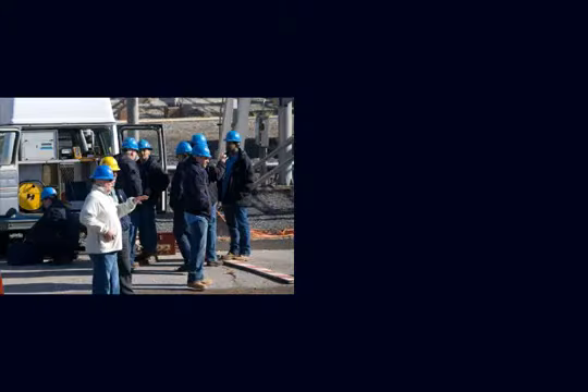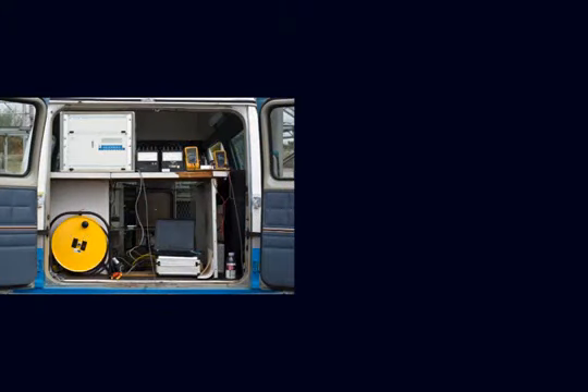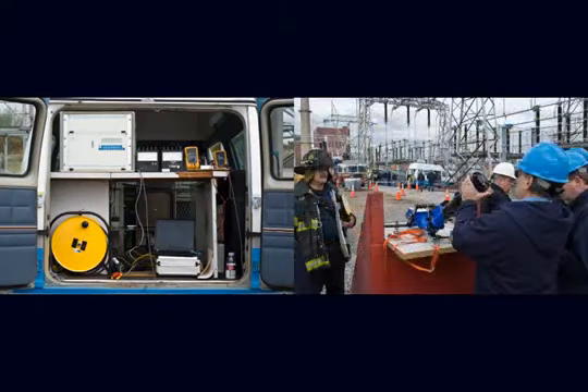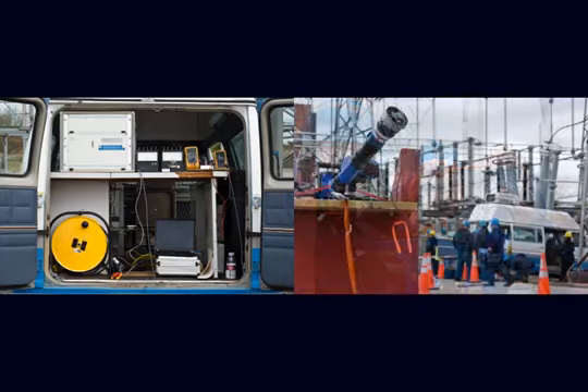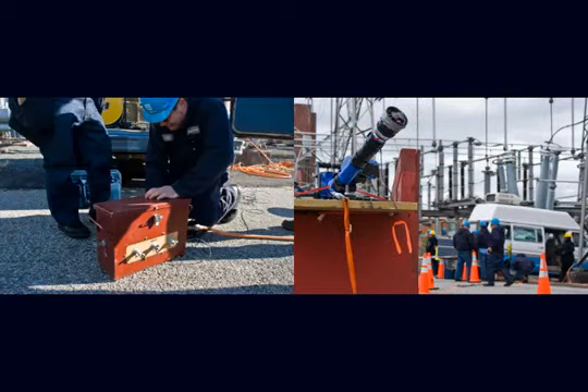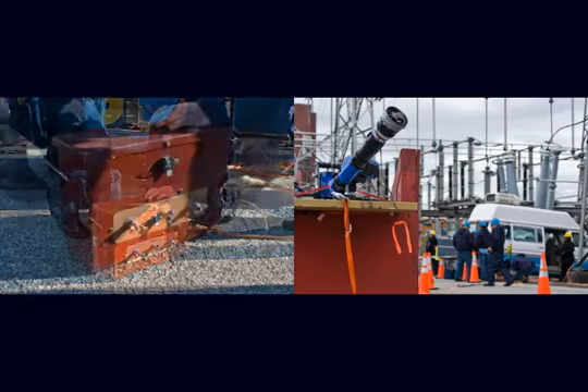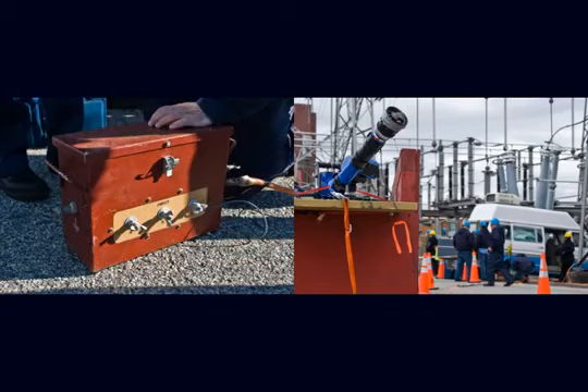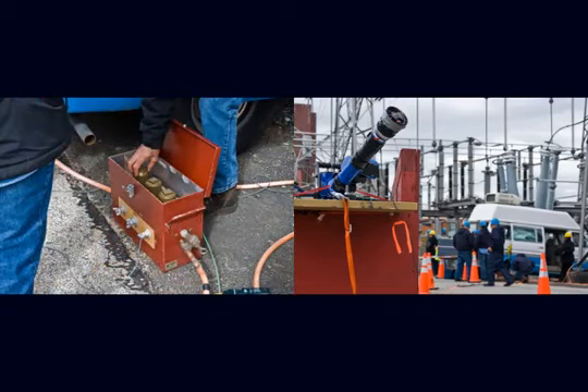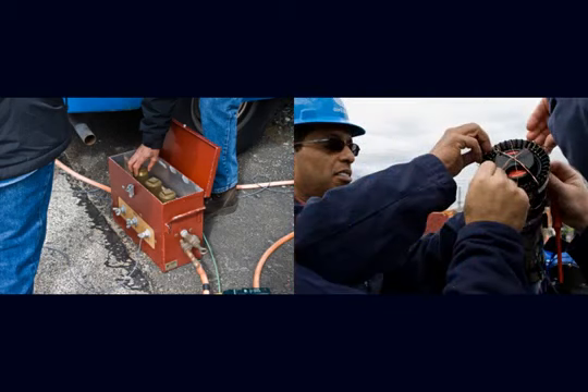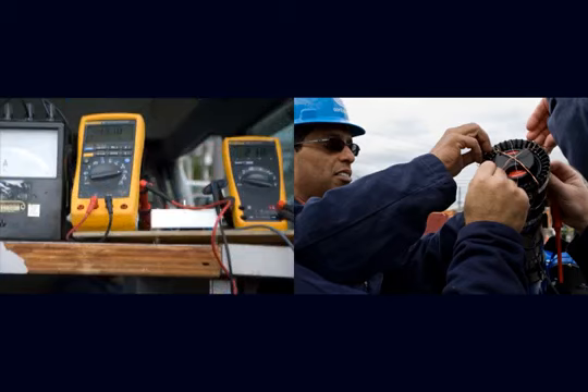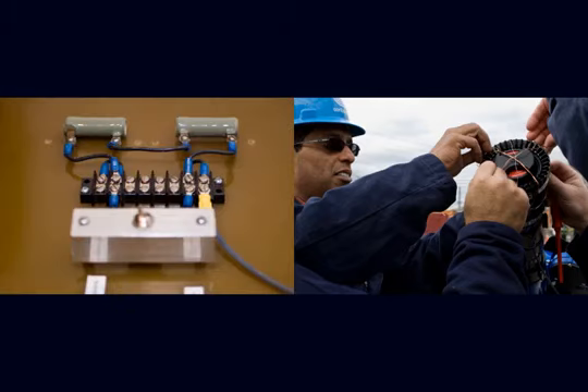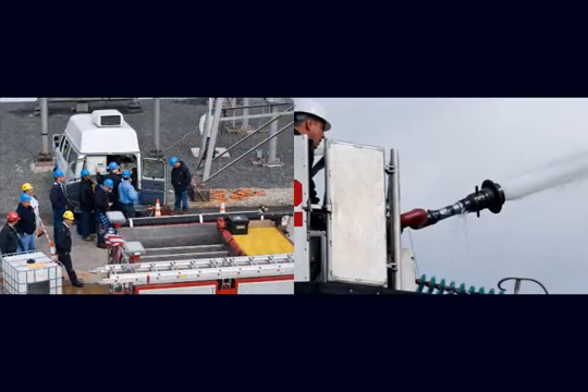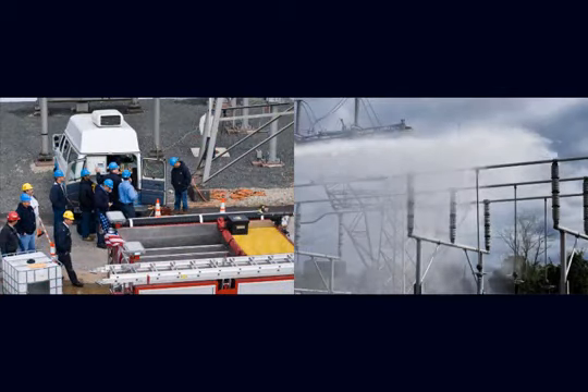What we ended up doing was we set up a portable van at the substation, regrounded it, and then stretched wire to the nozzles. We also installed the safety gap, which is very important in limiting any voltage coming back to the equipment, preventing any damage or potential safety hazards. The wire that was connected to the nozzles was run back to a 5,000 ohm resistor, which simulates someone holding that nozzle. We were able to measure current coming back from the F500 concentrate and water mixture.